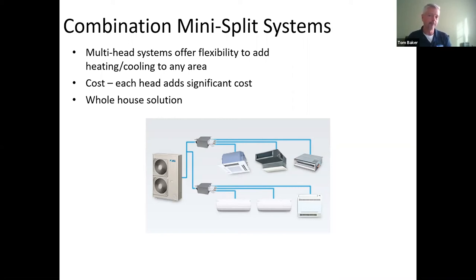And the big important priority here is to size the system properly for your house. So when we go into a home, we do a room by room heat loss calculation. And everywhere we're going to put one of these heads, we determine exactly what is going to be needed on the coldest days of the winter and the hottest days of the summer. We use government-set design degrees based on our temperature dynamics in the Northwest of 47 degrees for our average winter day and 17 degrees for the low end of winter. So if we do our job right and we put the right equipment in, the answer to your question is no. There's not going to be any diluting of the power between the three heads.